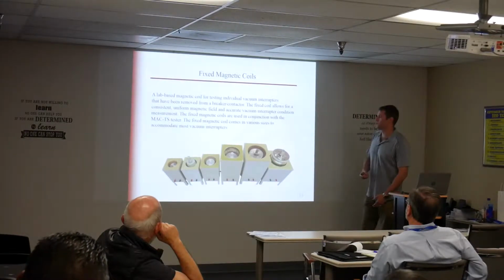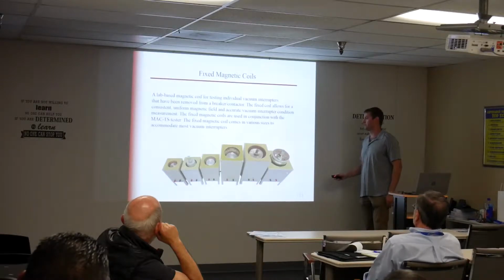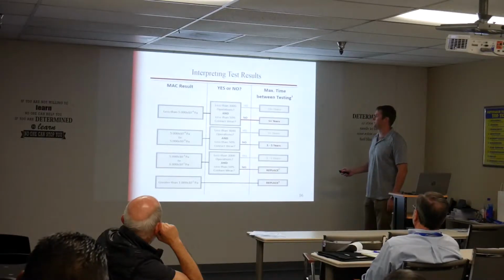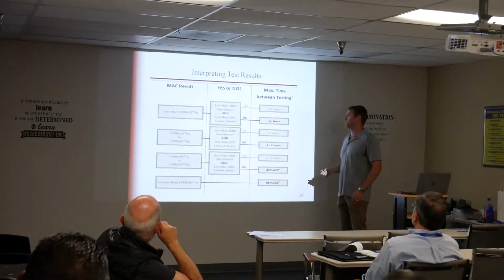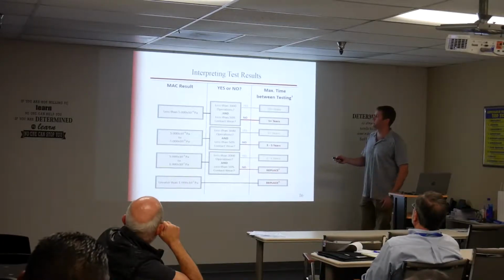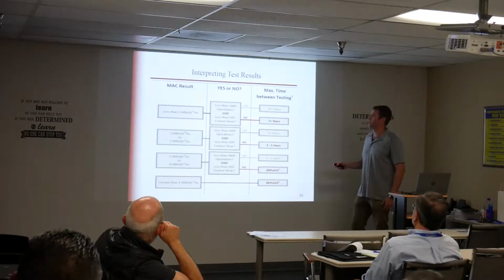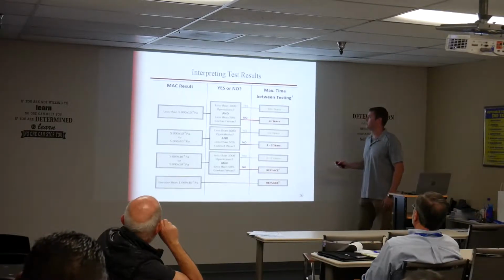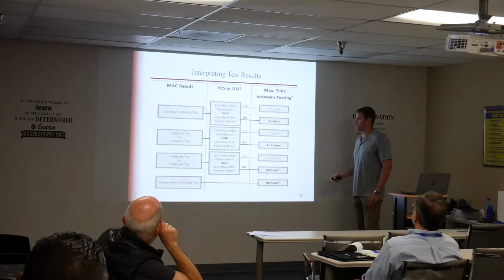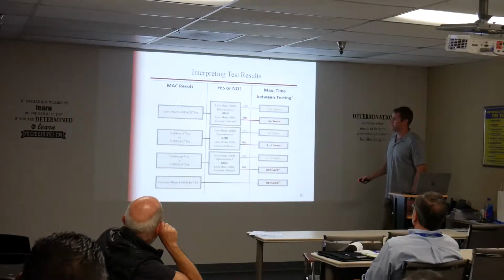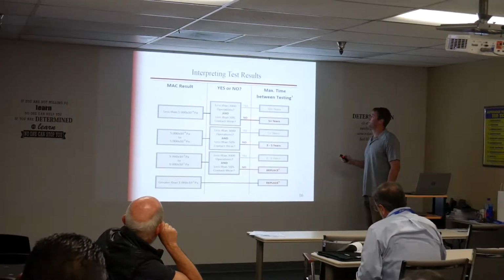The other part of our company is we do manufacture vacuum interrupters. This is how we test them in the lab. This is our interpreting the test results. Like I said, our test sets can output a pressure in pascals, but the 2 other things we look at are operations and wear. With those 3 things, we can estimate the life remaining or when you should worry about running another test. Like I mentioned down here, the -2s, it fails at -1, so the -2s are where we recommend replacing.